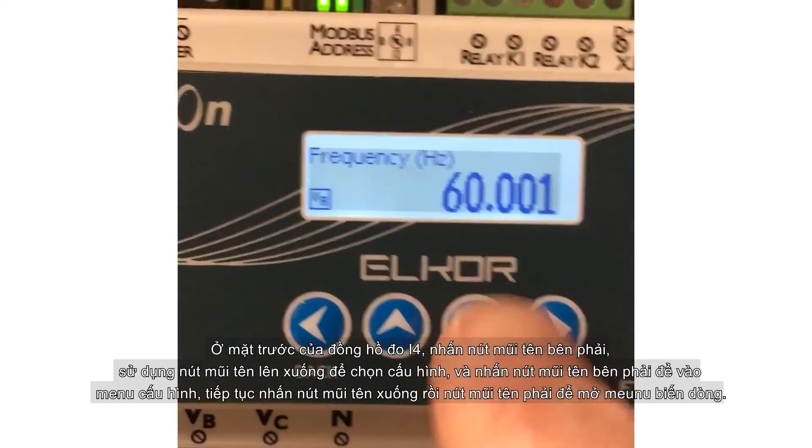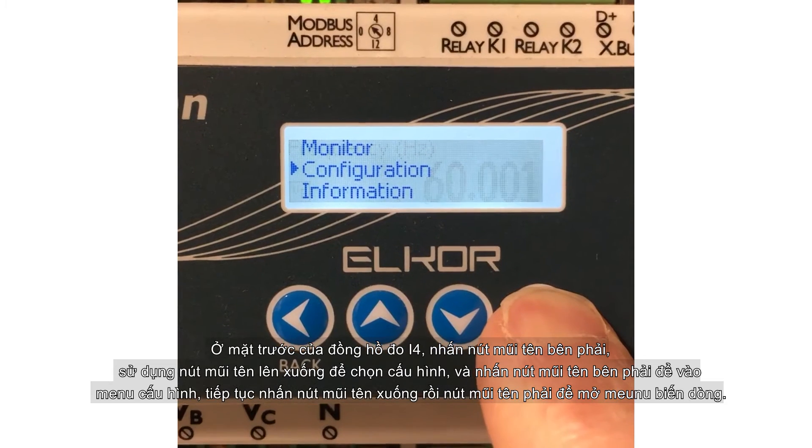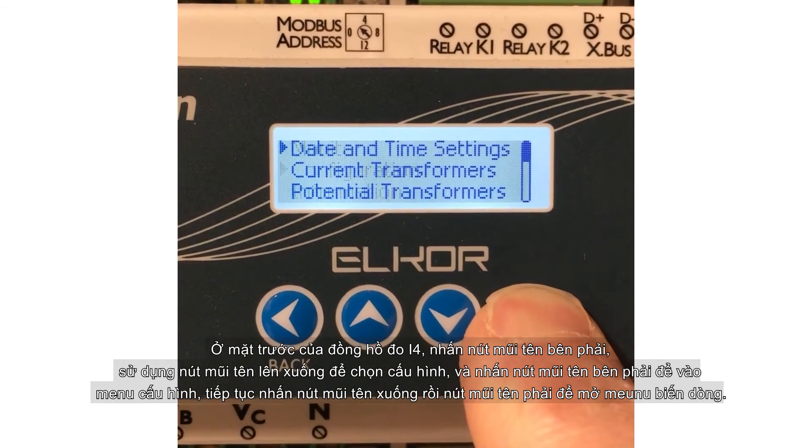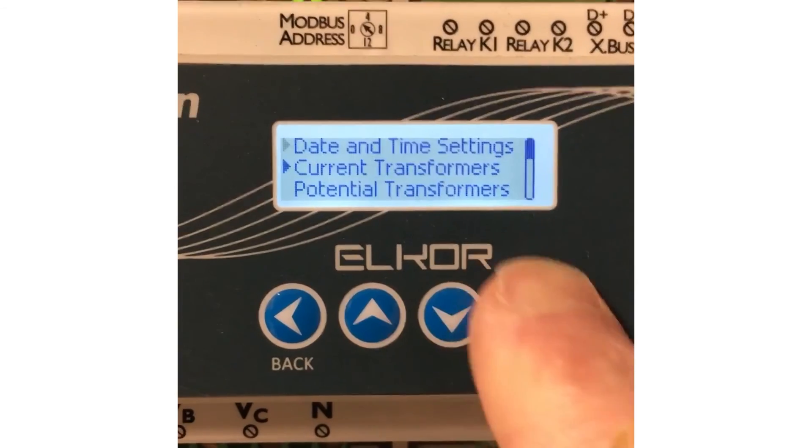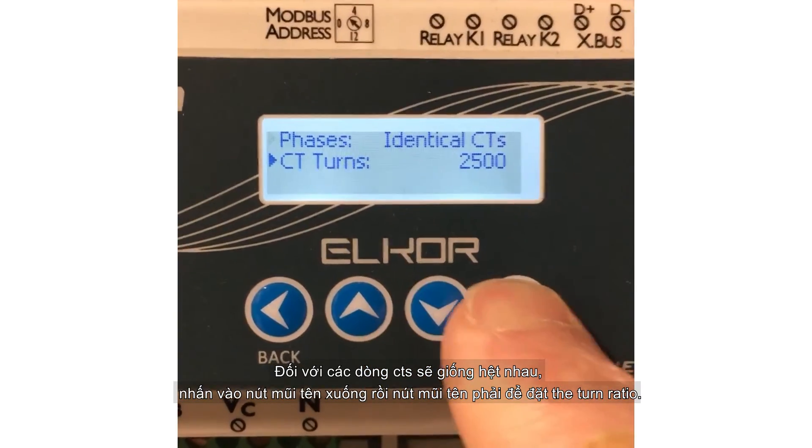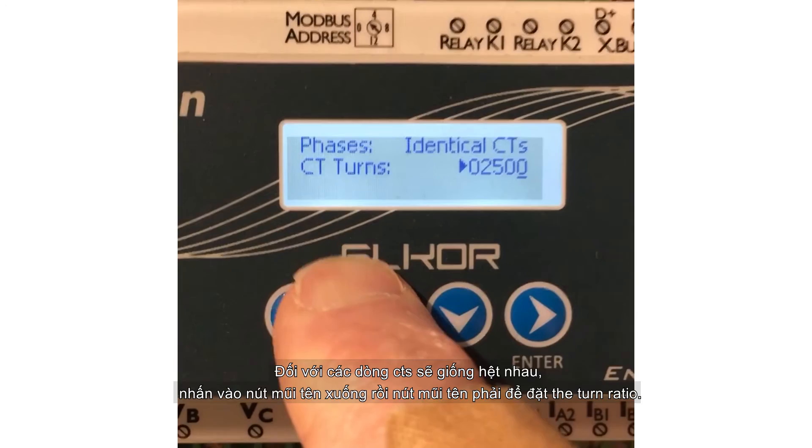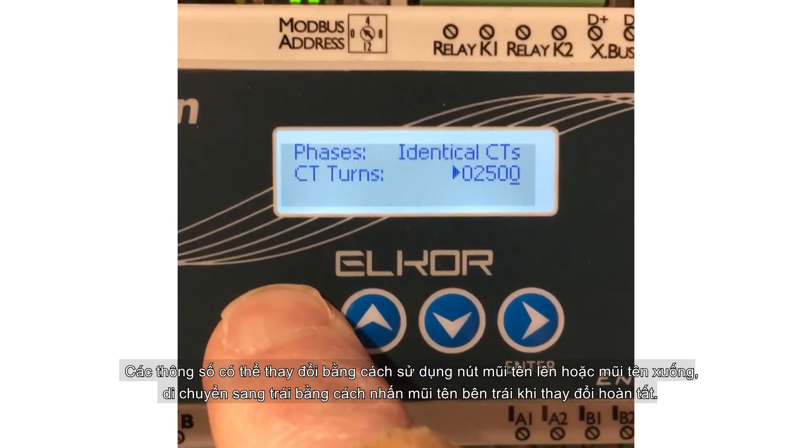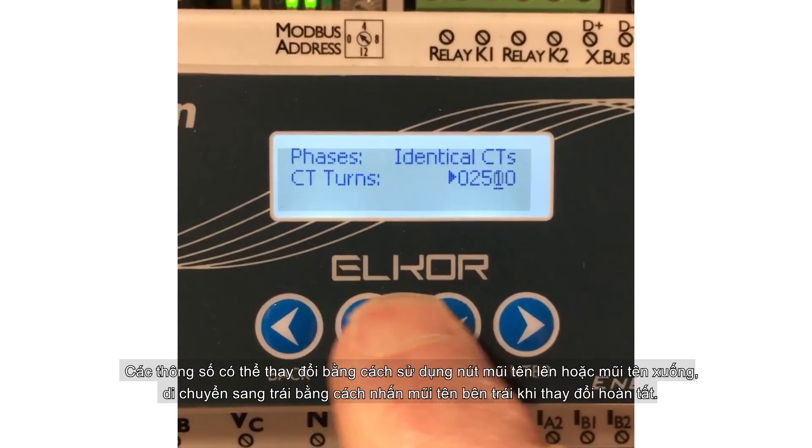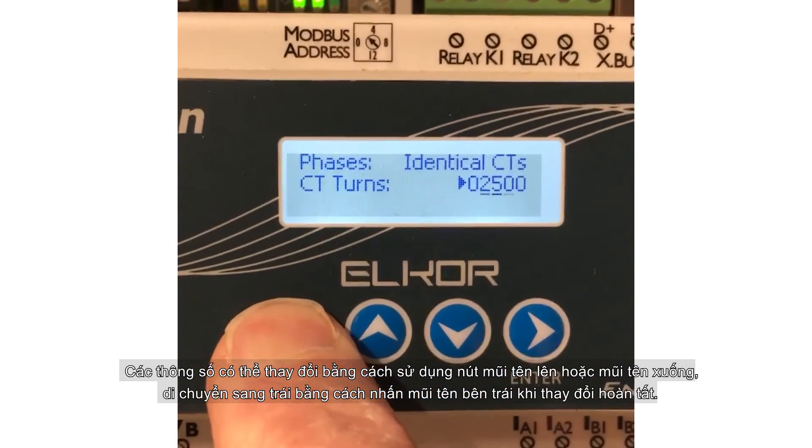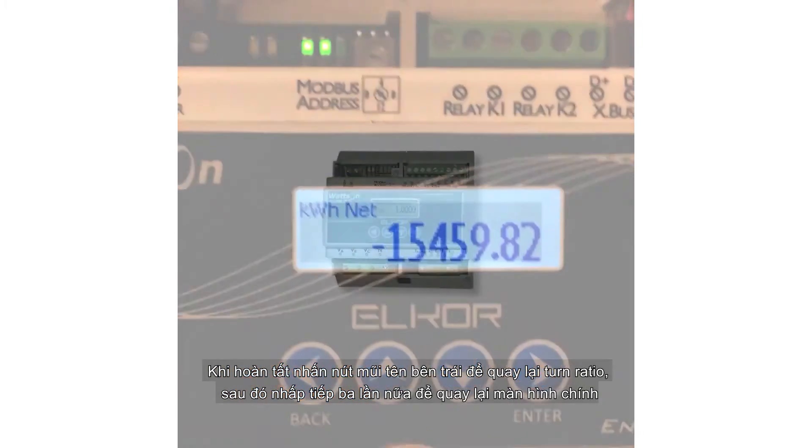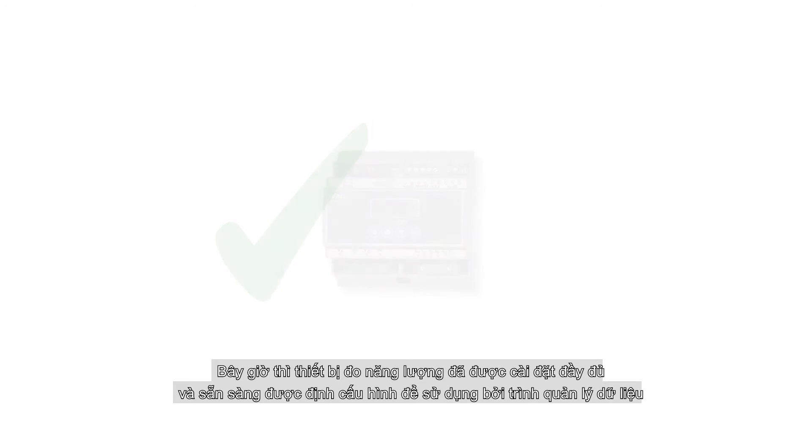Press the down arrow, and then the right arrow to open the current transformer menu. For identical CTs, press the down arrow, then the right arrow to set the turns ratio. The digit with the line beneath it can be changed by pressing the up or down arrow. Move to the left by pressing the left arrow. When done, press the left arrow until CT turns is selected, then three more times to return to the home screen. Now the energy meter is fully commissioned and ready to be configured for use by the data manager.